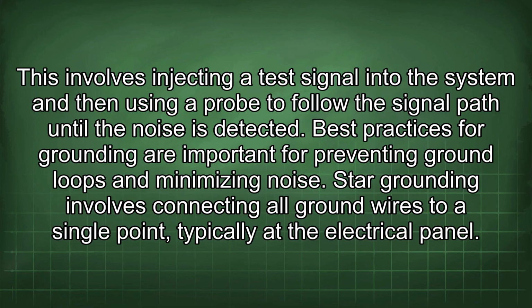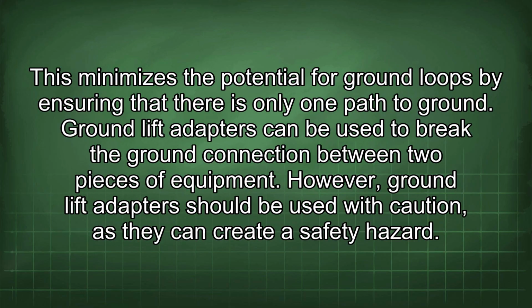Star grounding involves connecting all ground wires to a single point, typically at the electrical panel. This minimizes the potential for ground loops by ensuring that there is only one path to ground. Ground lift adapters can be used to break the ground connection between two pieces of equipment. However, ground lift adapters should be used with caution, as they can create a safety hazard.